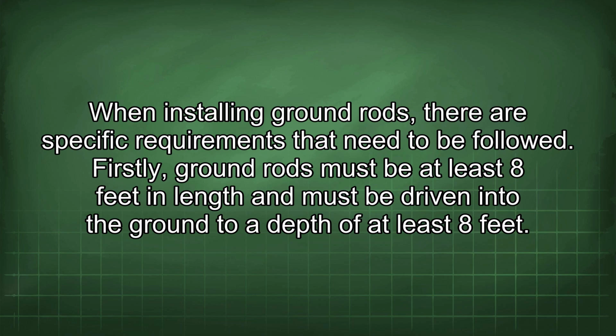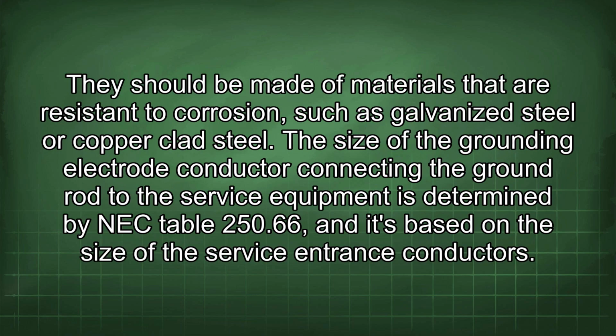Firstly, ground rods must be at least 8 feet in length and must be driven into the ground to a depth of at least 8 feet. They should be made of materials that are resistant to corrosion, such as galvanized steel or copper-clad steel. The size of the grounding electrode conductor connecting the ground rod to the service equipment is determined by NEC Table 250.66, and it's based on the size of the service entrance conductors.